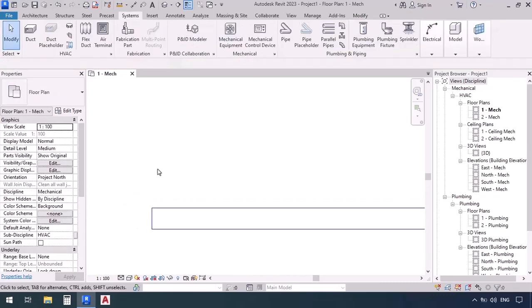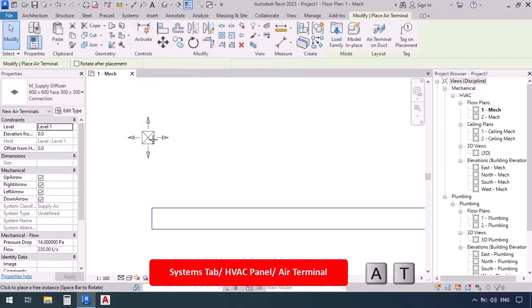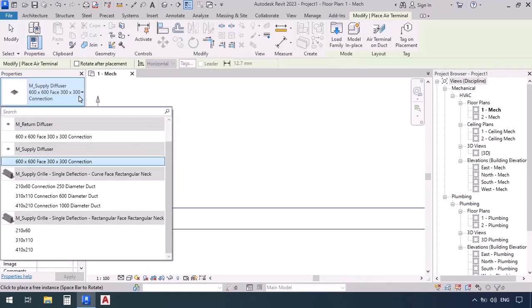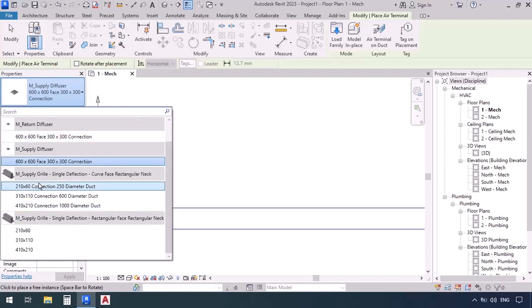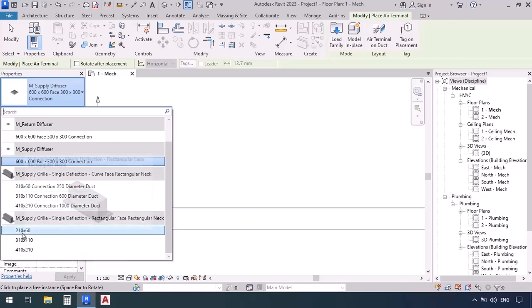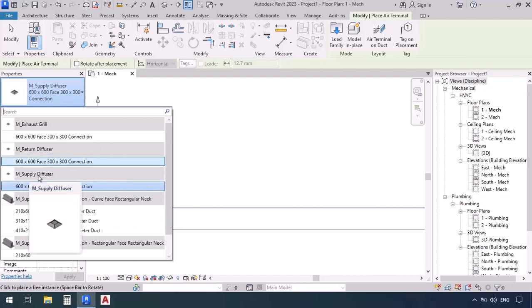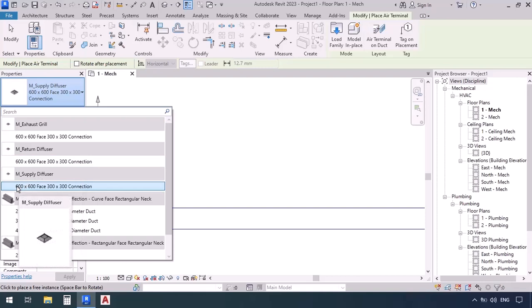Now we want to place some terminals right next to it. Go to the systems tab and click on the air terminal command. In the properties window we can see the family for the loaded terminals. In this template we have one exhaust grill and return diffuser, as well as supply diffuser, and two other types of supply grills — one with a curved face and one with a flat rectangular face. We'll use the supply diffuser, which has a square shape with dimensions 600 by 600 face, meaning 60 by 60 centimeter surface, and a 300 by 300 connection.